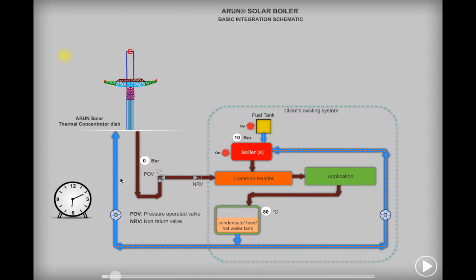The basic aim of the control system on the solar side is to deliver steam from the Arun solar boiler to this existing boiler header. The Arun solar concentrator dish automatically tracks the Sun from morning to evening. The solar radiation falling on the reflecting collector surface is concentrated at a single point at which the receiver is placed. The receiver coil at the focus of the dish transfers the heat of the Sun to the heat transfer medium, which is water in this case.